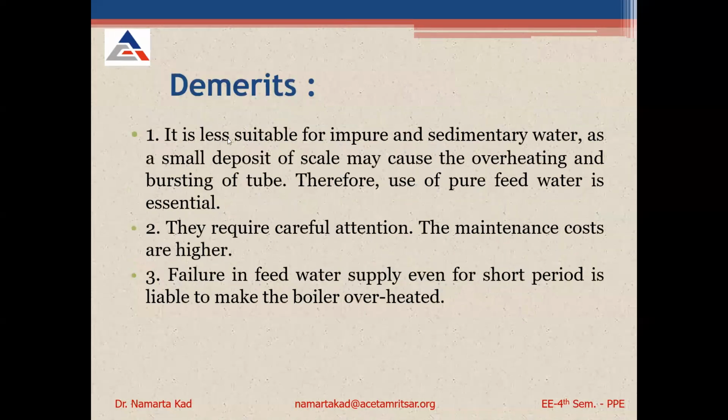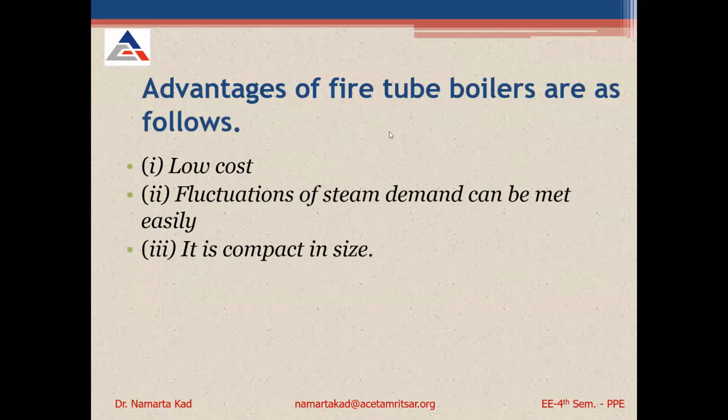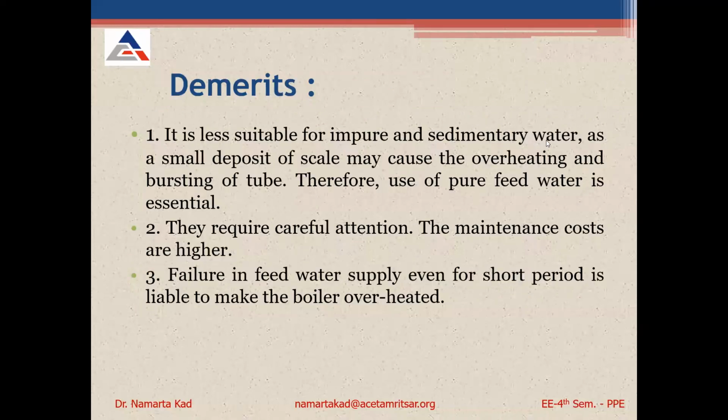And the demerits are, it is less suitable for impure and sedimentary water. Water pure होना चाहिए, उसमें डस्ट पार्टिकल्स नहीं होने चाहिए. ठीक है, it must be pure water. Small deposits of scale cause overheating and bursting of tubes. ठीक है, use of pure feed water is essential. They require careful attention. The maintenance costs are higher.